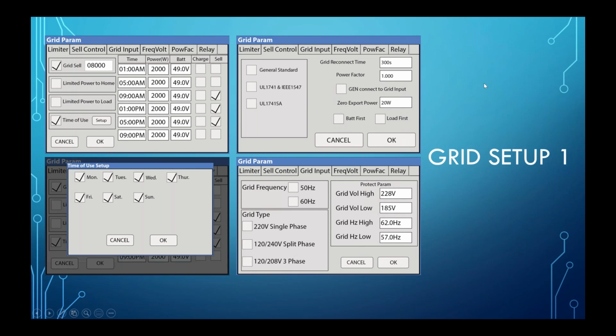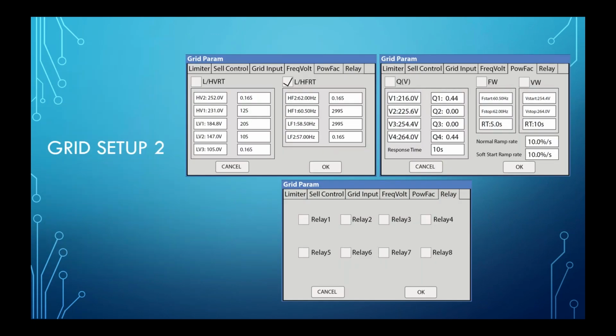Awesome. Thank you, Dustin. So the second part of this, Dustin, I know this is going to be pretty quick, but if you would just give us a little bit of color as to these screens. Yep. Absolutely. Again, these are very important if you're trying to do something specific. We do have the ride-through frequencies and ride-through voltages, if certain grids require them. These are the sections where you would set those. Power factor and the relay tabs are actually very rarely used. The power factor tab is if you're AC coupling, and the relay tab is going to be for later use down the road. We don't necessarily use that currently, so just keep those in mind as they are located here once we release some information.